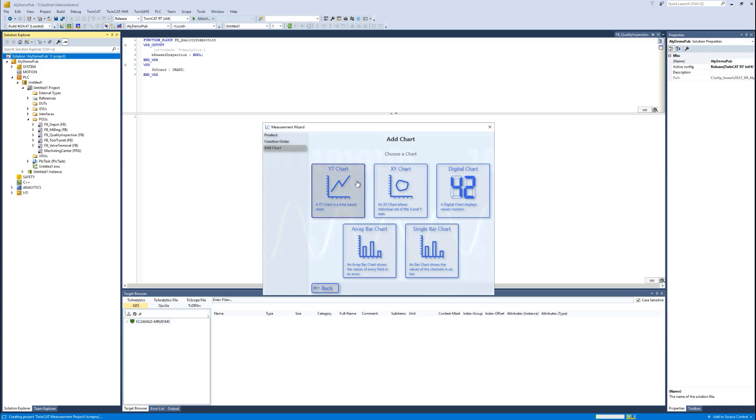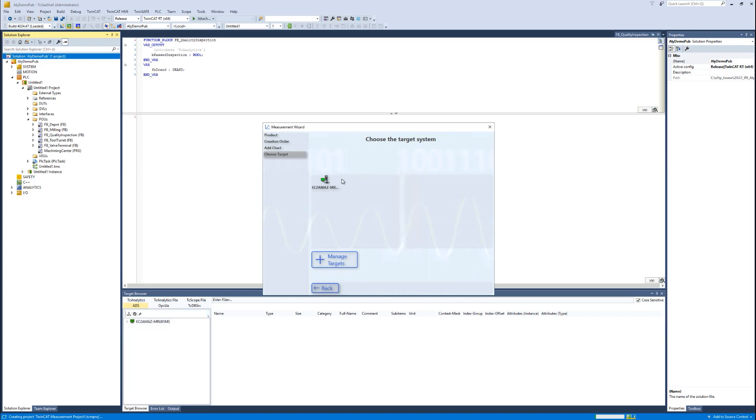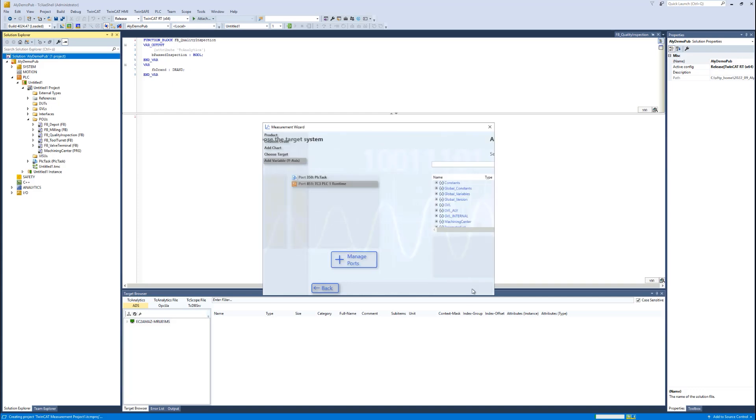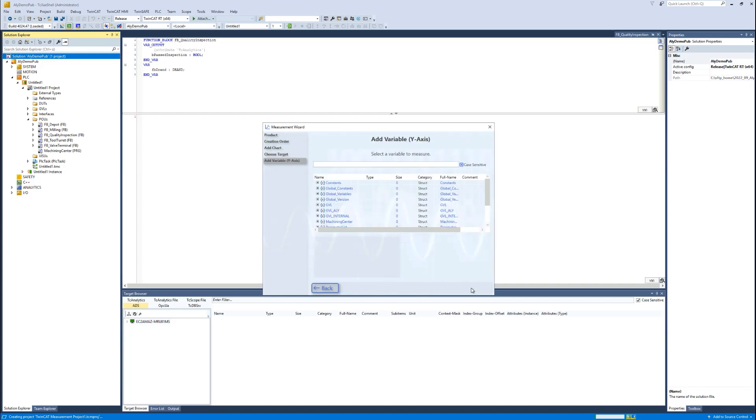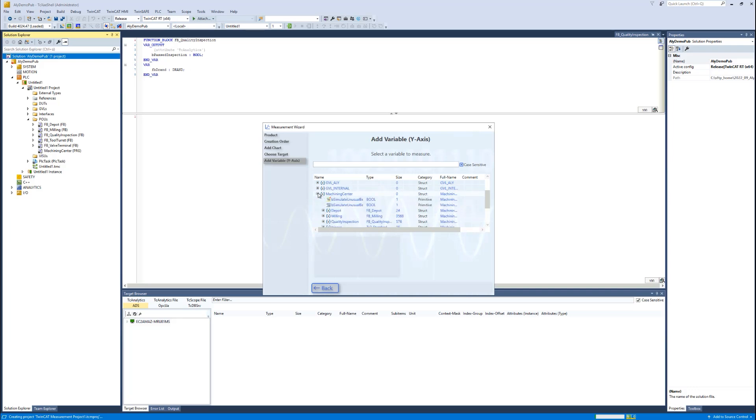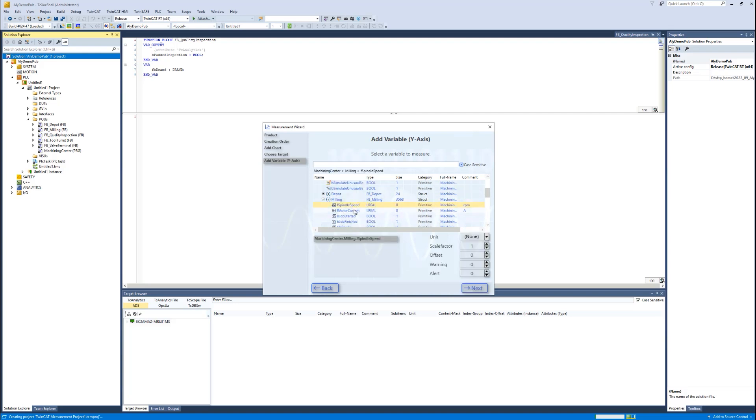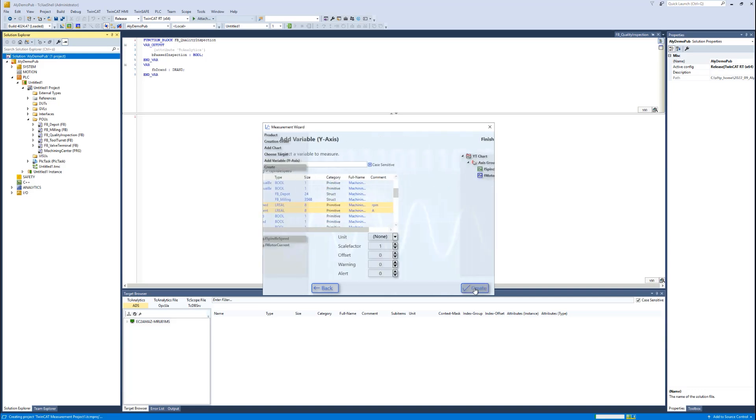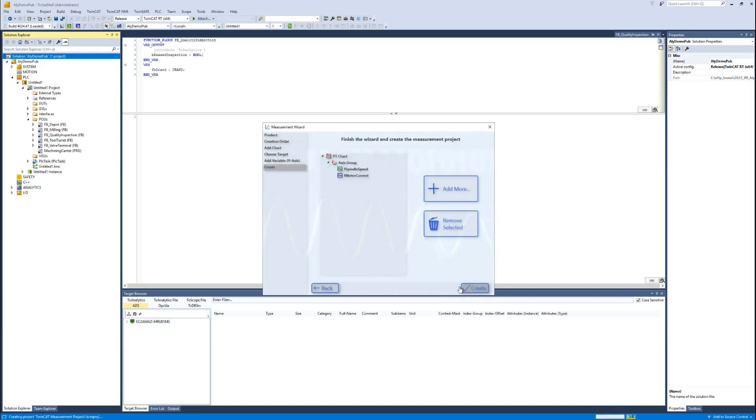I can choose my target system and I can choose a port for the symbols. In this case, the PLC port. Then I can browse into this port and can choose different variables. I go to the milling machining center, milling part of the machine, and then I choose the spinning speed and also the machine current. Then I have a preview here. I can directly create this as a configuration for scope or I can add here in the wizard some more charts, and I choose this option.